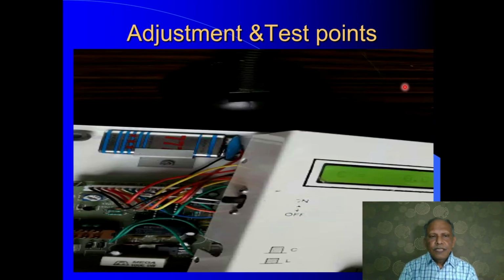Now we will see the adjustments and the test points. Already I explained about the test points. The only adjustment in the LC meter is the contrast adjustment. There is no other calibration adjustment within the LC meter, as it has an auto calibration facility. Now let us look at the video.